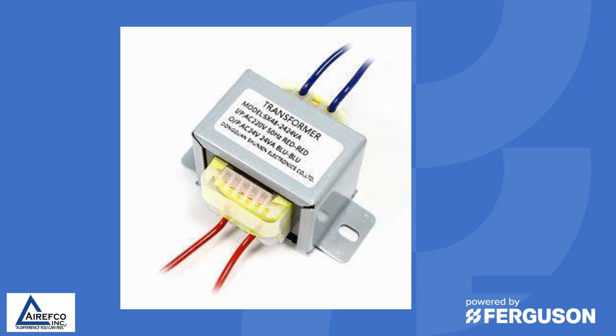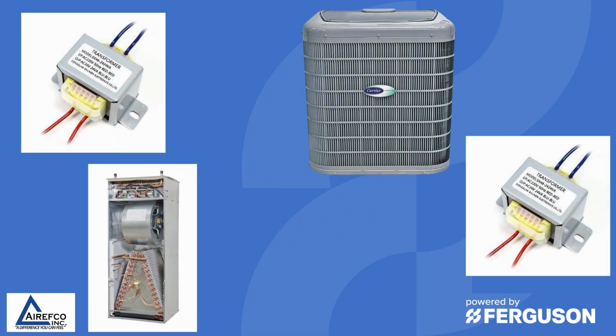In this video, we're going to talk about properly phasing transformers in an HVAC system. In a lot of the equipment that is being put out in the field these days, there is a transformer normally in the indoor unit, the fan coil or the furnace, but there is also sometimes a transformer in the outdoor unit. So keeping the voltage from these two transformers separate is something that a modern technician needs to keep in mind.